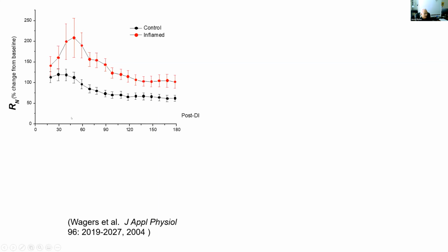So the animals were just mechanically ventilated over this time, but every 15 seconds or so, was it 15 or 20 seconds? I can't remember. We would switch the ventilator from ventilating into oscillating. And that's what this FlexiVent can do. You can interrupt ventilation anytime you want and use it as a system identification test bed. So we would pull off an impedance measurement in 2 seconds, about every 15 seconds. And from that, estimate those 3 parameters of the constant phase model.